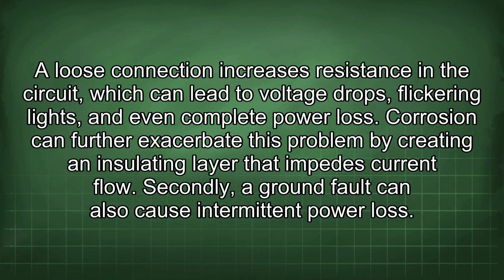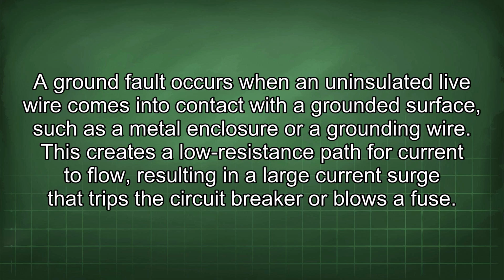Secondly, a ground fault can also cause intermittent power loss. A ground fault occurs when an uninsulated live wire comes into contact with a grounded surface such as a metal enclosure or a grounding wire. This creates a low resistance path for current to flow, resulting in a large current surge that trips the circuit breaker or blows a fuse.